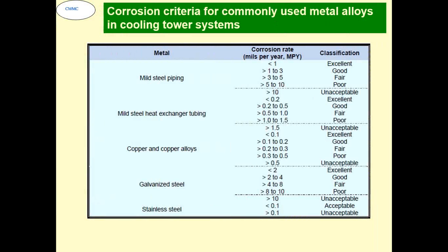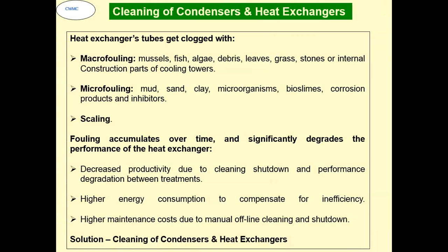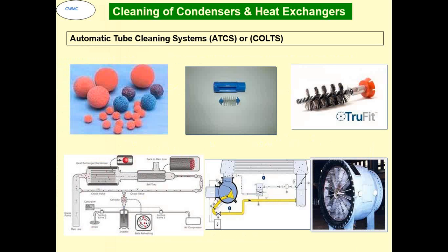These are the limits for the corrosion. Cleaning of heat exchangers: microfouling is there, scaling is there. Normally online tube cleaning systems consist of a sponge ball system, brushes, or different kinds. They are run through the system and keep running continuously, cleaning the tubes. These kinds of systems are very good for soft scale, sludges, and biofouling. But if hard scale is there, then they are not effective, because they are not able to remove the hard scale.